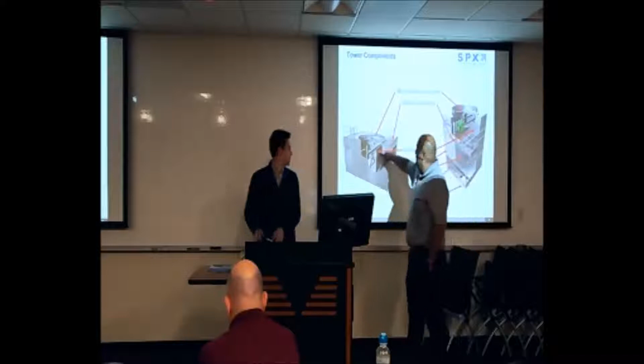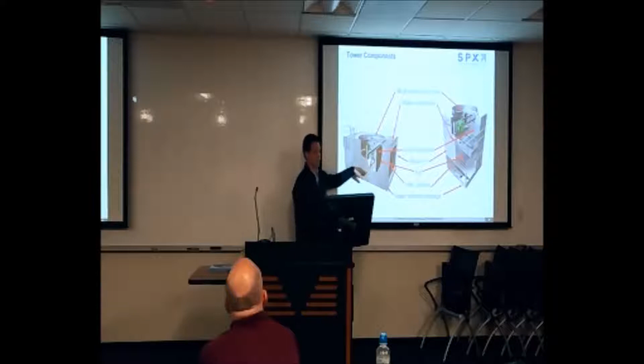Do you want to talk about the catwalk area? So I didn't talk about structure at all, but the main maintenance area for the crossflow towers—and you guys should be very happy that you have a crossflow tower to do maintenance on instead of a counterflow tower—because the crossflow towers have an access door right here, and from this access door you will have a plenum walkway catwalk basically. From there you'll be able to access your drift eliminators, your fill, your mechanical, your motors, your gear reducer. You'll be able to do a lot of your work within that mechanical access platform. With the counterflow, all the components are stacked on top of each other, so it's much more difficult to find points of entry to do maintenance.